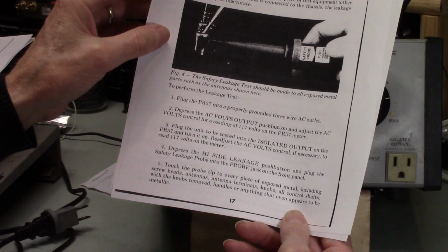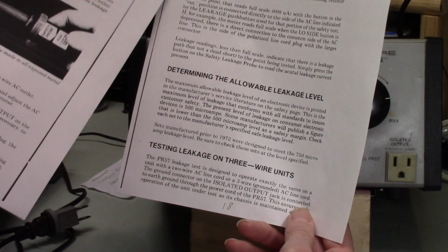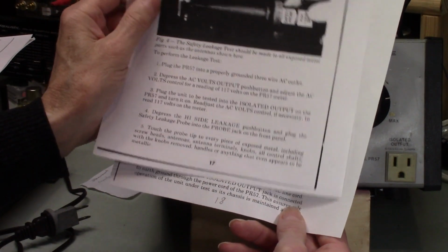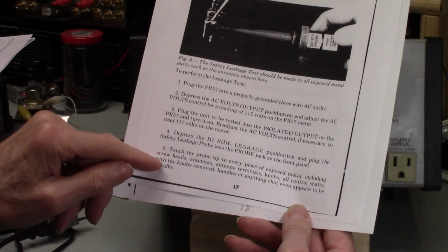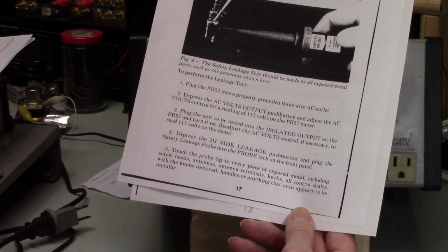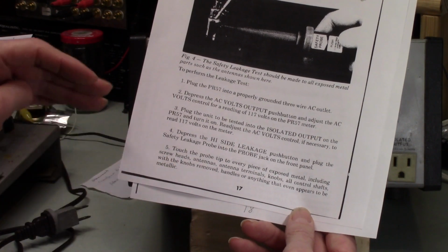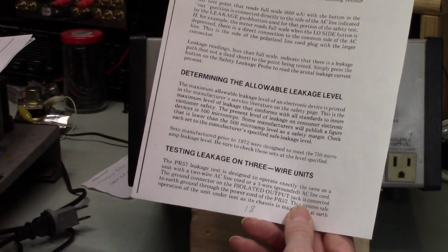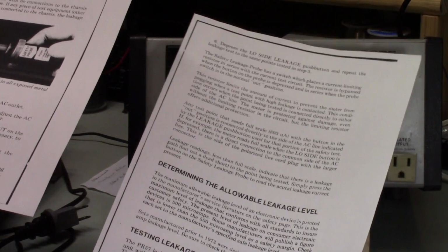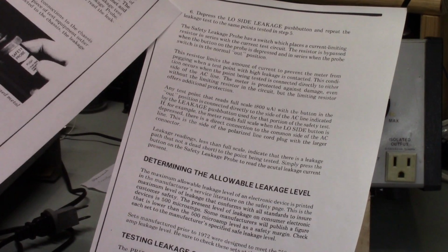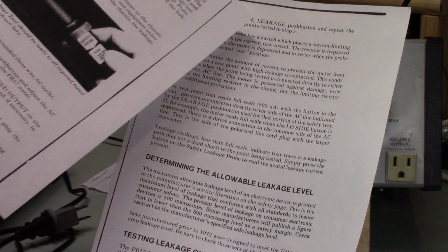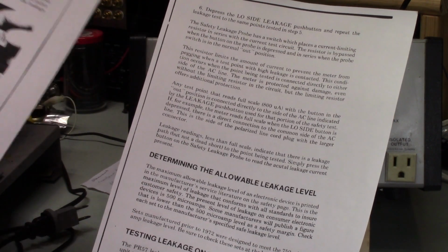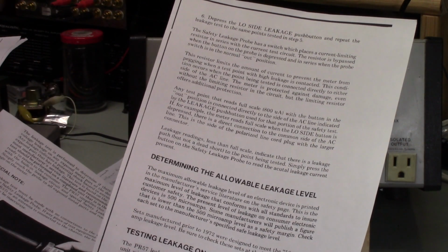And here's why I disagree. They talk about touching the probe to every piece of exposed metal, including screw heads, antennas, antenna terminals, etc. Then they tell you to press the low side leakage push button and repeat the test. We will do that.